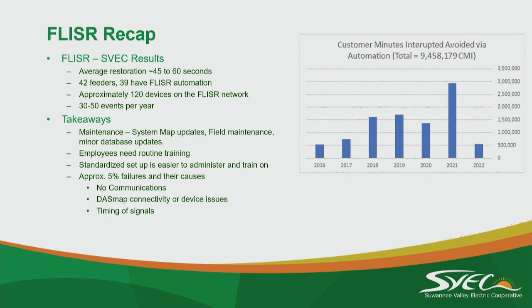You've got to keep training employees. If they don't see it and they don't use it, they forget it. Part of what this has given us is the ability to backfeed a substation outage, but that one's done manually right now. Our operators have to know how to identify substations out, whether it's okay to backfeed, and check if the correct devices are showing open. There's no fault flags—why didn't FDIR backfeed this? Why didn't FLISR backfeed this? They have to identify what it should backfeed, what it can't backfeed, and we usually get 1 or 2 of those big substation outages a year. If you're not practicing and preparing them, they're going to miss the opportunity to save all that time of an outage.